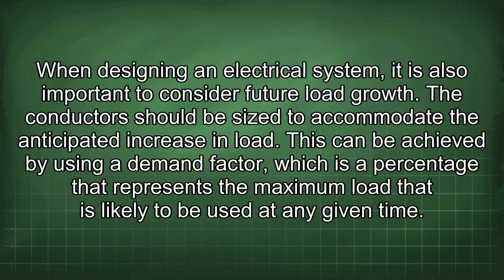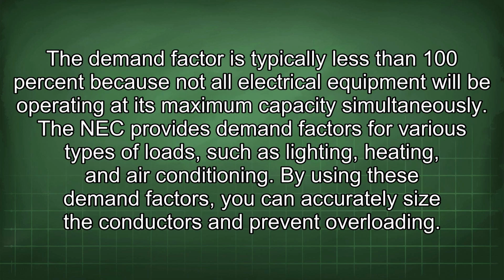When designing an electrical system, it is also important to consider future load growth. The conductors should be sized to accommodate the anticipated increase in load. This can be achieved by using a demand factor, which is a percentage that represents the maximum load that is likely to be used at any given time. The demand factor is typically less than 100% because not all electrical equipment will be operating at its maximum capacity simultaneously. The NEC provides demand factors for various types of loads such as lighting, heating, and air conditioning. By using these demand factors, you can accurately size the conductors and prevent overloading.